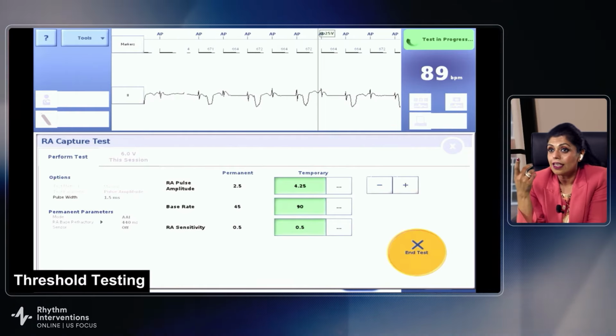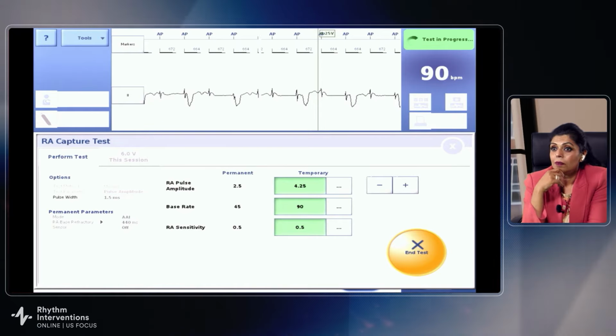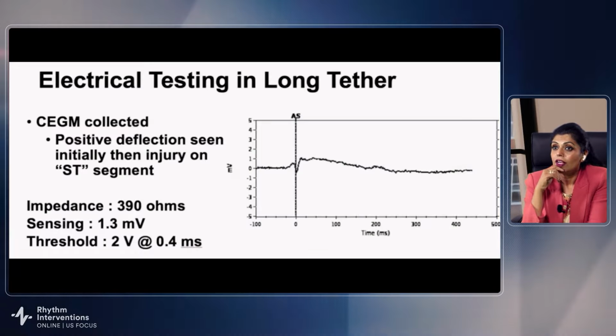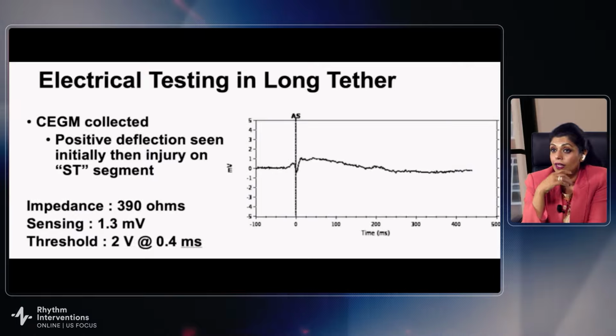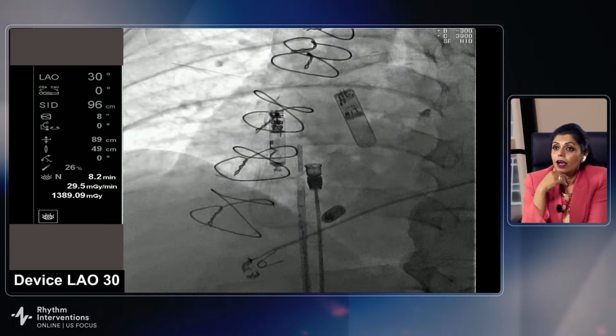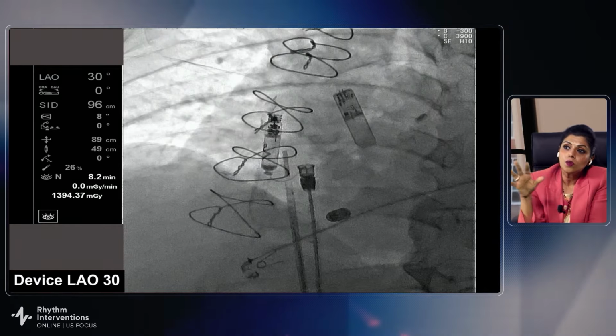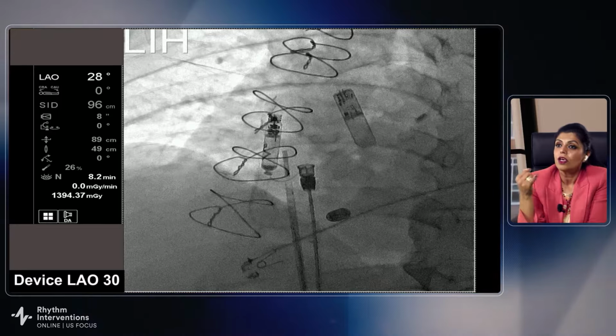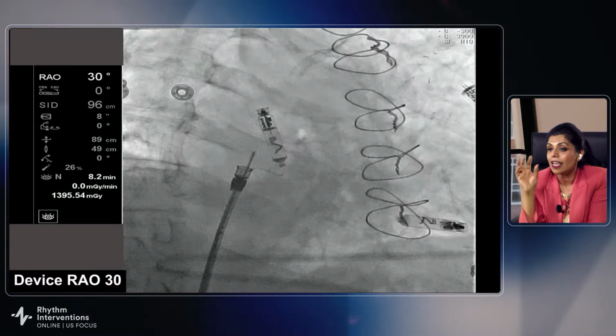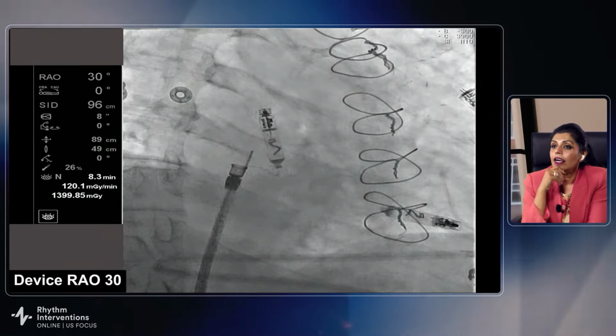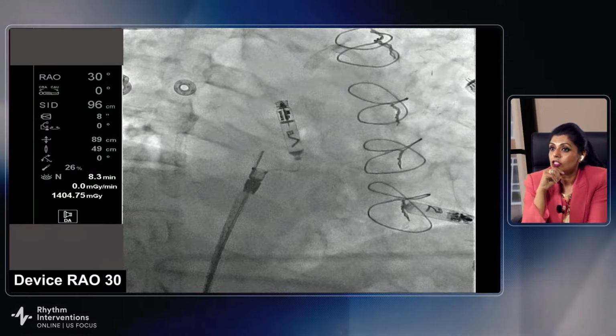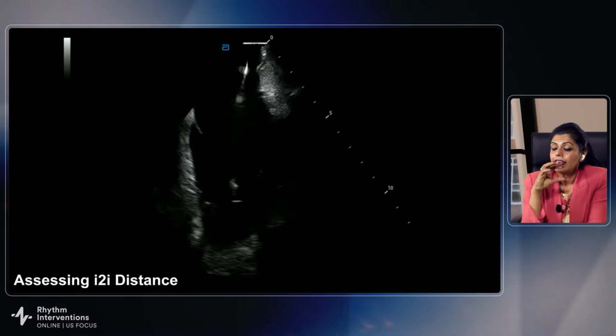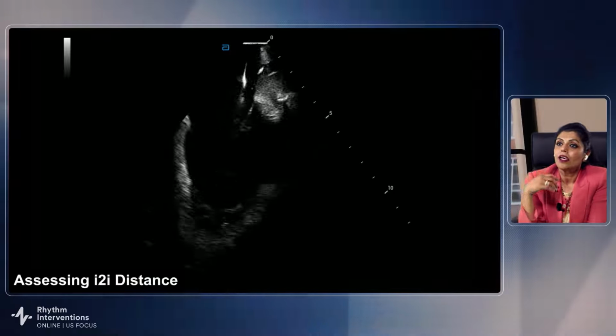You can clearly see I'm pacing at about 90, and the patient is in heart block. So definitely a candidate for dual chamber pacing. So glad that we started off that way. But again, you can see once we have good electrical parameters, we've seen good mechanical stability. Again, looking at that chevron and the helix to make sure there's stability and good implant characteristics, we're ready to release the device.